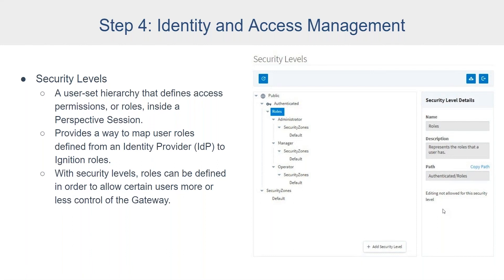Complex security level rules can also be created using Ignition's expression language, where a security level can be derived from the authentication or authorization context itself. This context can take into account who you are — your logged-in user identity and profile attributes — where you are, your assigned security zones, and what roles you have. It can also take into account the current time of day, in case users can only log into a system between the hours of 8 a.m. and 5 p.m. Pacific, for example. You're only limited by your imagination — it can be really powerful to write these expressions for even more granulated security.